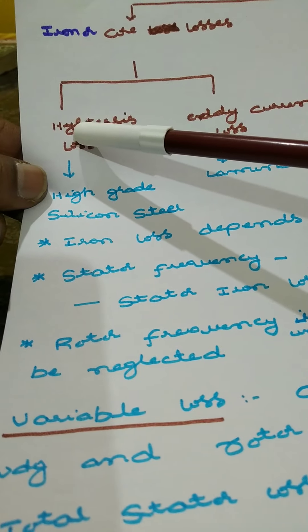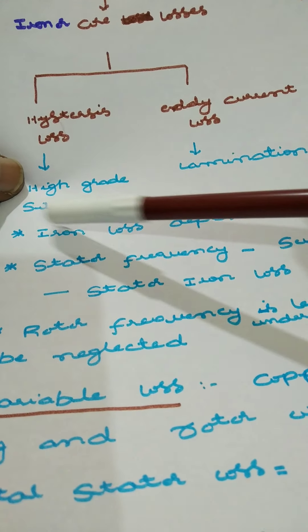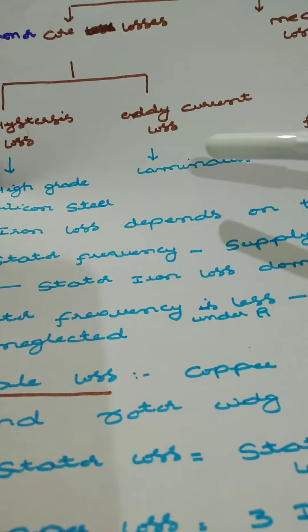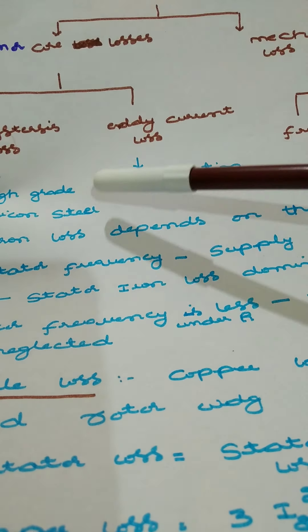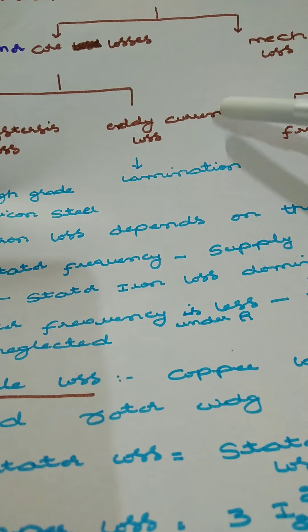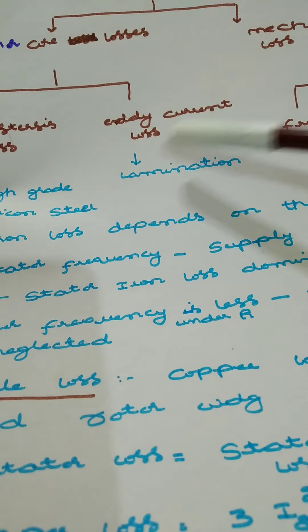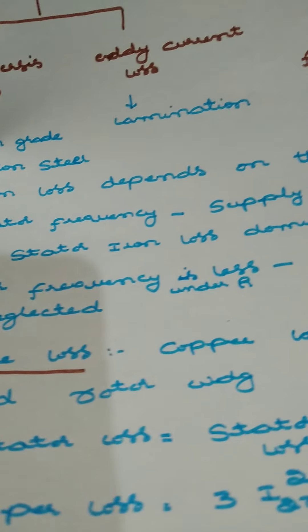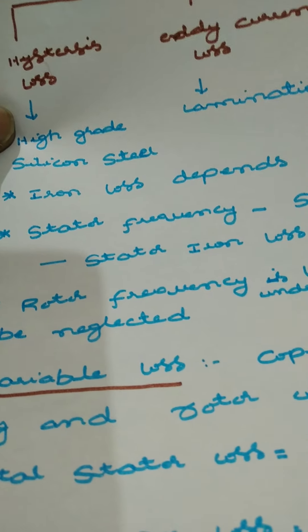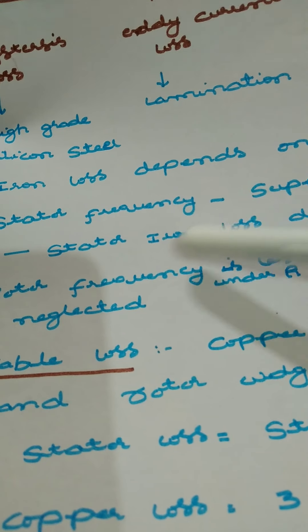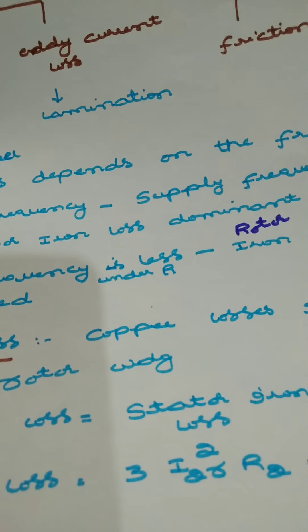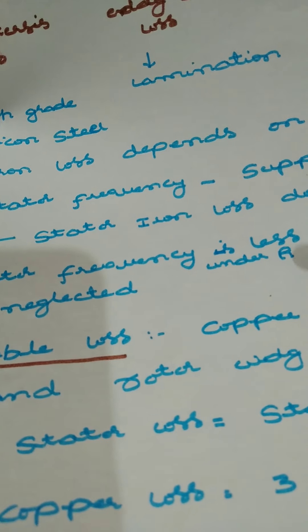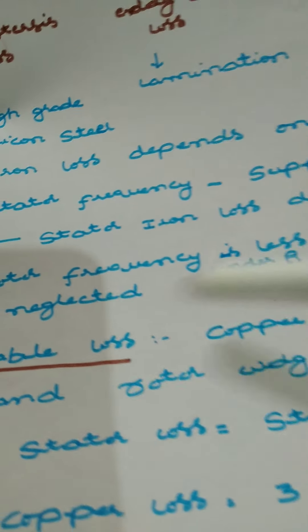Hysteresis loss can be minimized by using high-grade silicon steel. By making the core in laminations, you can reduce eddy current losses. Core loss depends on frequency. Stator frequency is always equal to supply frequency, therefore stator core loss is dominant. Rotor frequency is less under running conditions, therefore rotor core loss can be neglected.